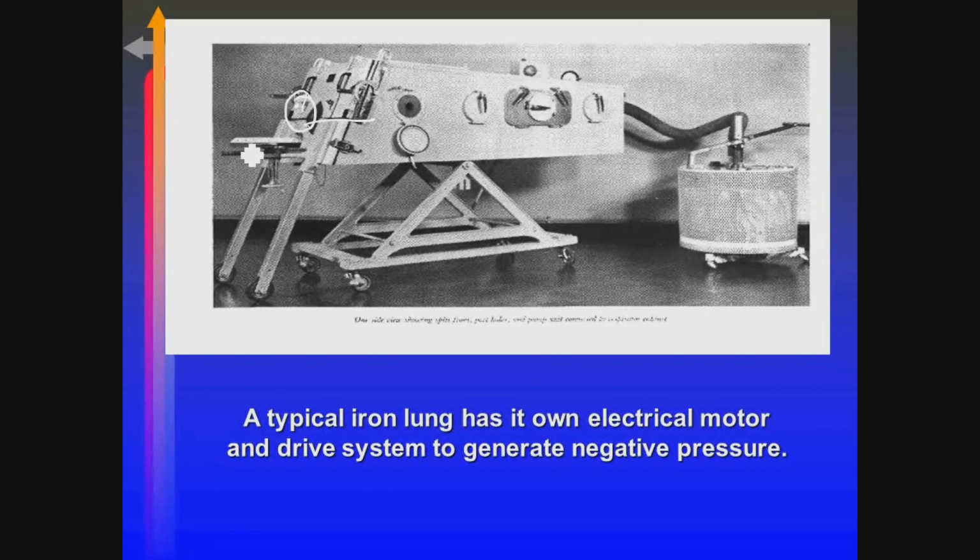Okay. Anybody want to venture a guess what this is? It's a handle. Why? We lose power. Exactly. Pretty scary. And it's basically just a big vacuum. That's all it is. Turn the vacuum on, create negative pressure, turn the vacuum off, goes back to zero.